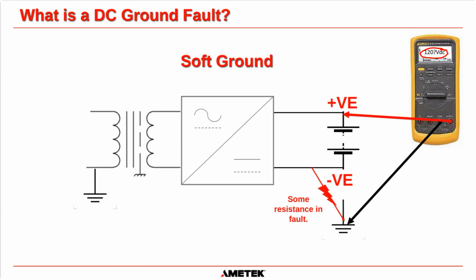So that's the difference between a hard fault and a soft fault. And I can't tell you what the values are going to be for a soft ground fault. It depends on the resistance of the fault itself. It could be 50 volts on one pole and 70 volts on the other. The lowest pole is the one that has the fault. That's what you've got to remember.